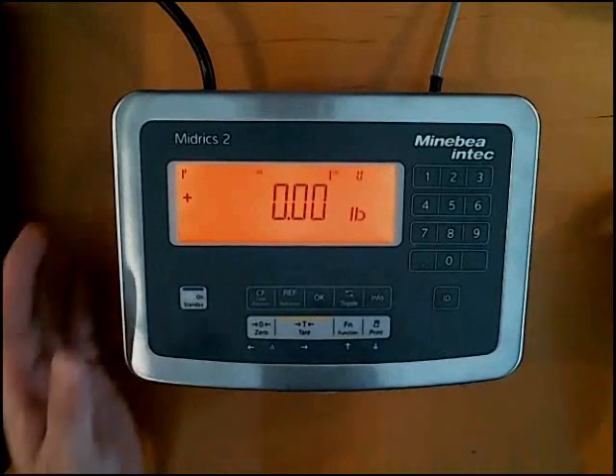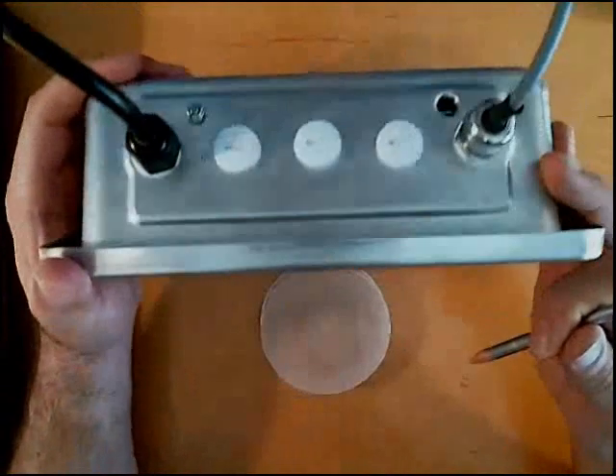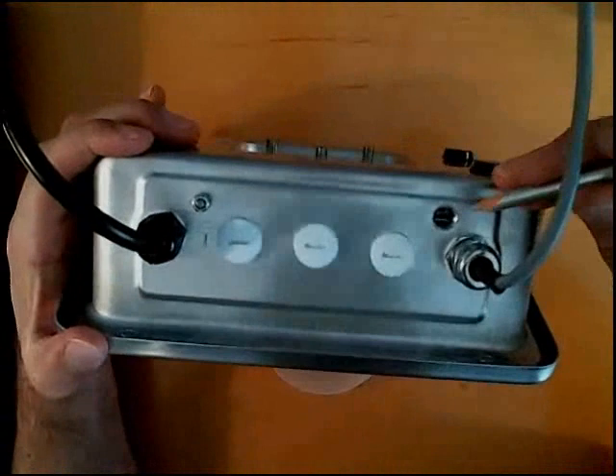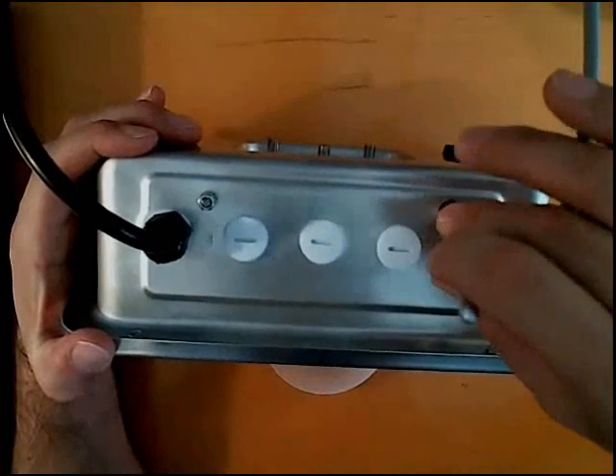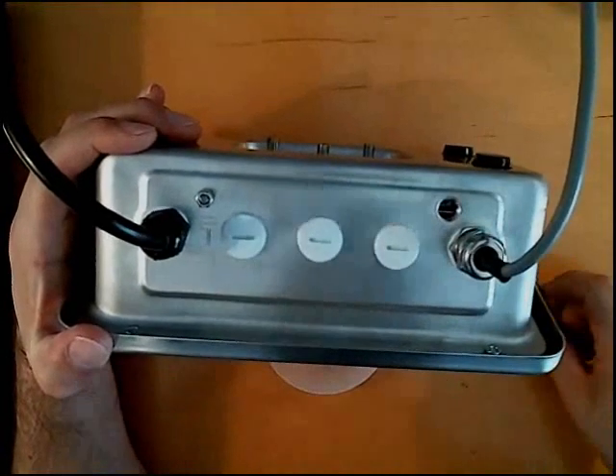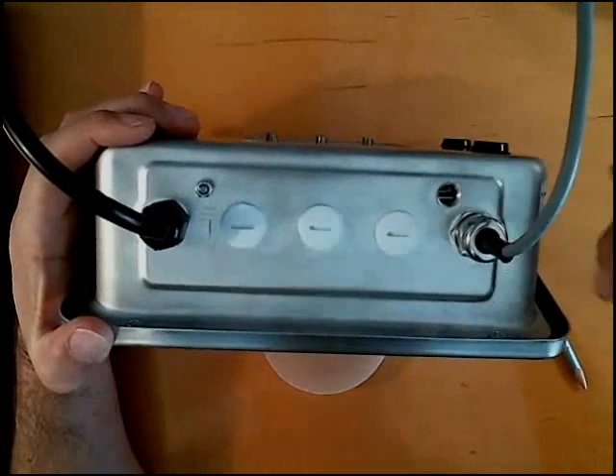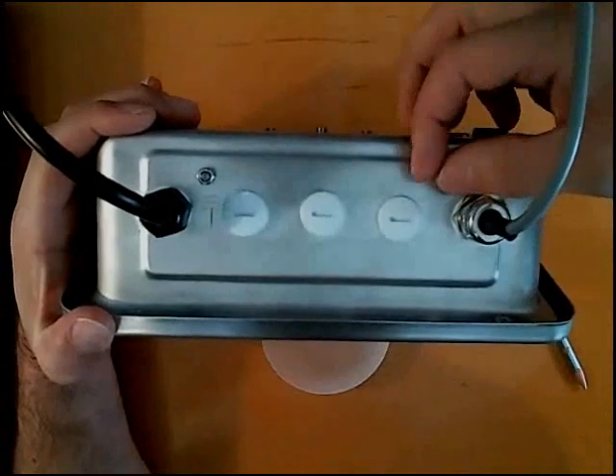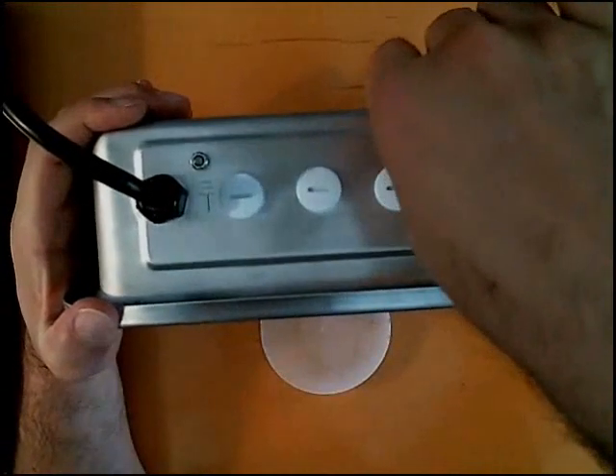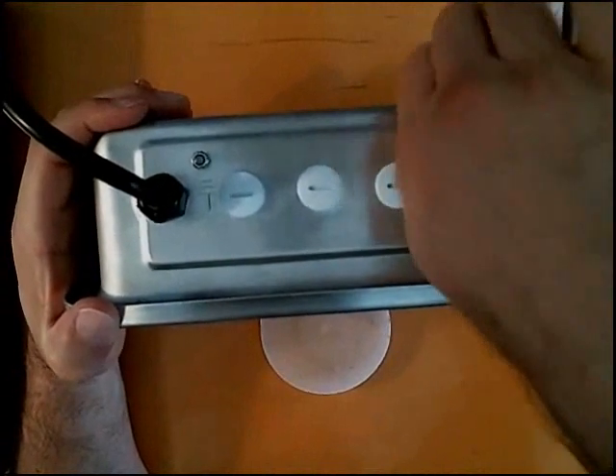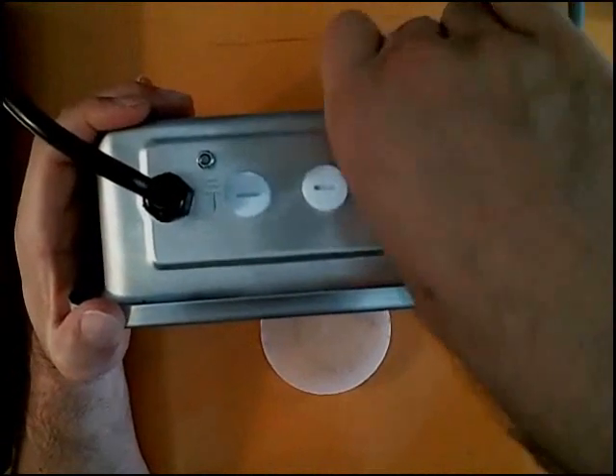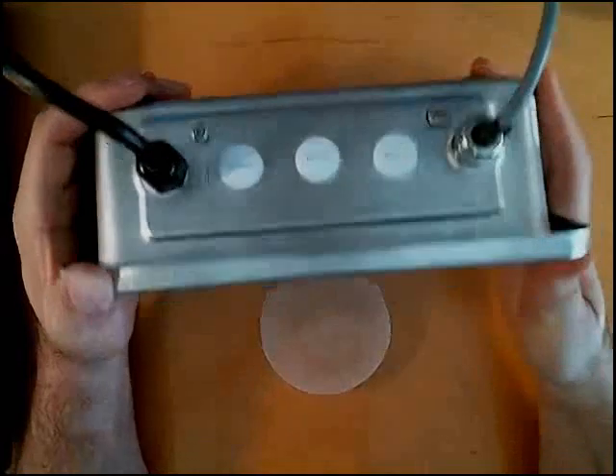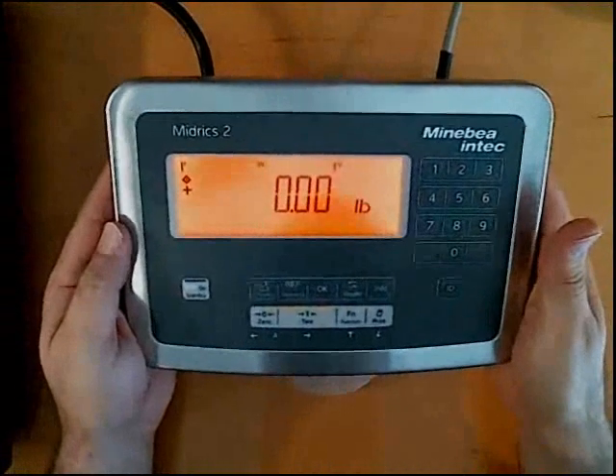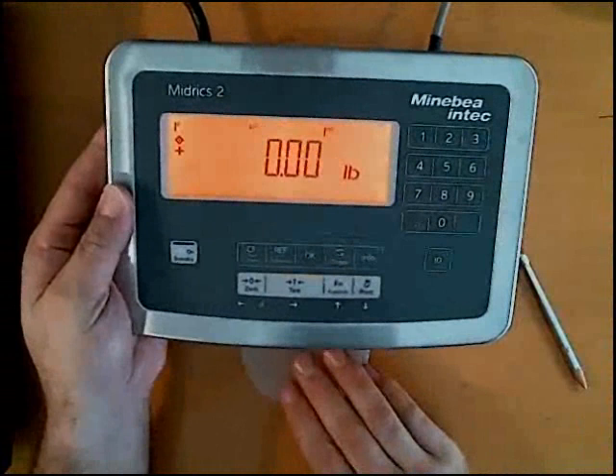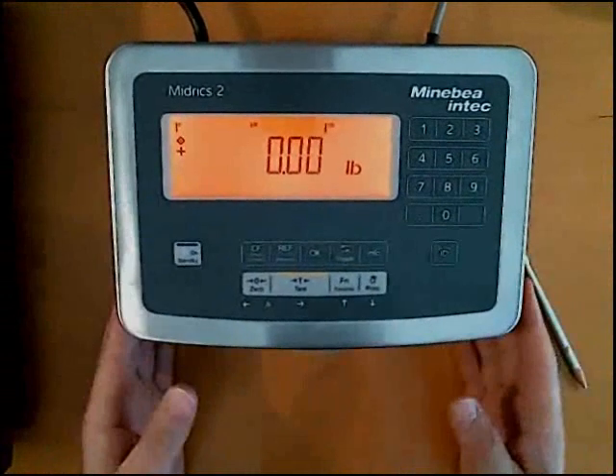Just keep in mind that you will need to go back here to your menu switch and move it over away from the home run cable, okay? Away from this cable. This will put you in the user mode, and that does a couple of things. Not only does it lock you out of the A to D converter, so nobody can go in and inadvertently make changes, it will also ensure that the scale shows 0 when it powers on, okay?